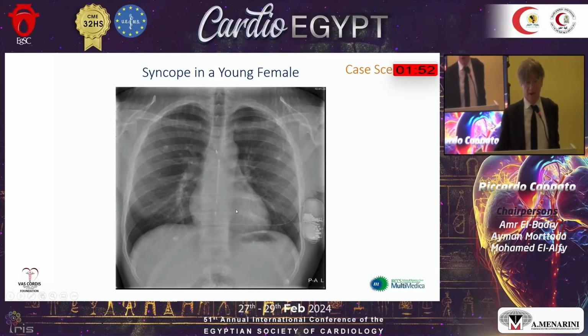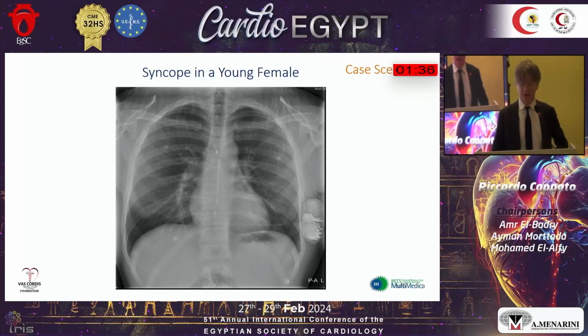A few words on the SICD. It's entirely subcutaneous in its currently available clinical form. The canister is located in the left hemithorax at the submuscular level, and it's connected through a wire to a lead electrode provided with two sensing electrodes and one defibrillator lead. And the shock is delivered between the central lead and the canister.